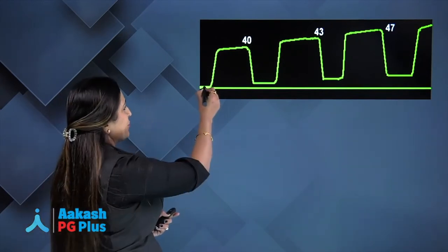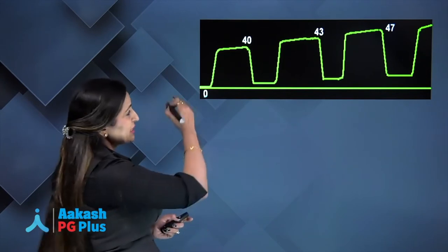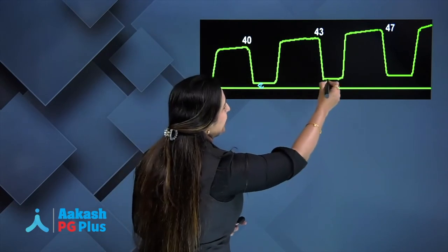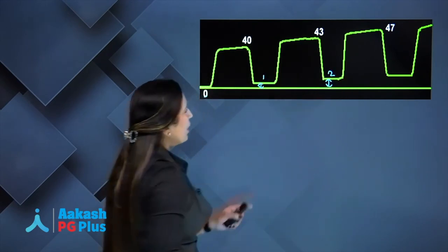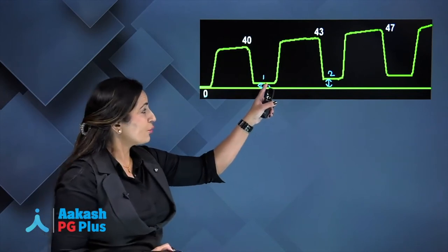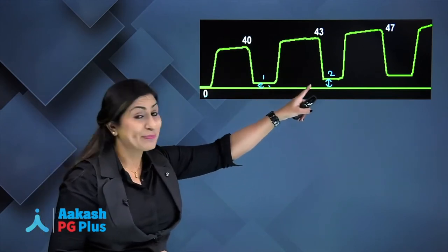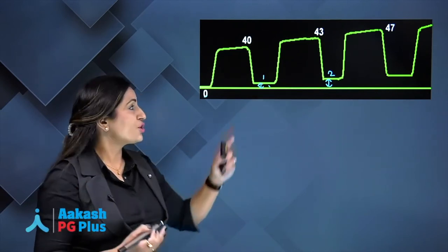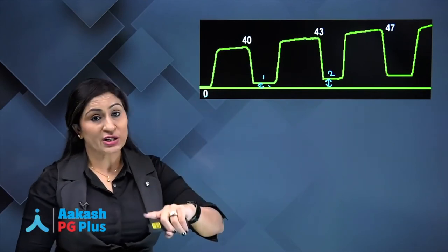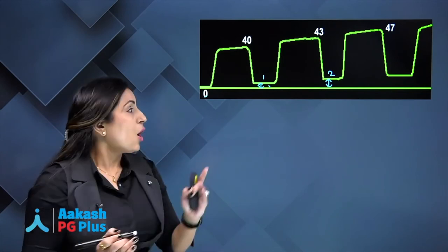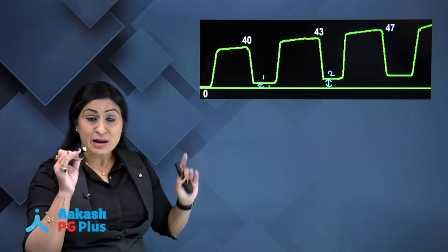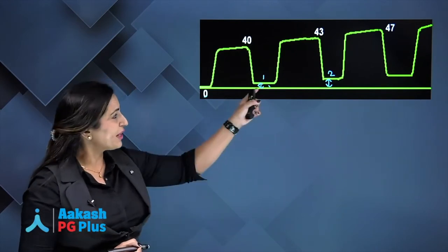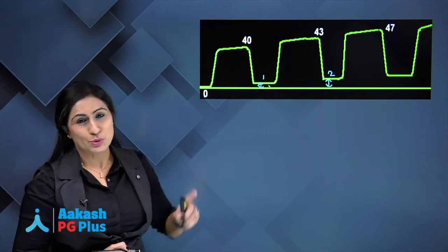When you see a capnogram where the baseline CO2, which should be zero, is gradually increasing with each ventilation — maybe rising to 1 or 2 — this shows that the patient is breathing in carbon dioxide during inspiration, which should not happen. This indicates that the soda lime has been exhausted or there is a fault with the valve, and you need to change your soda lime.